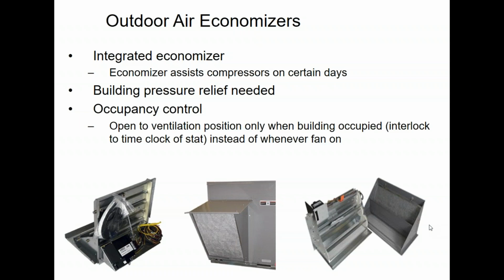Additionally, from a controls perspective, we need to have the ventilation damper close at night. Now, most of you guys know the economizer has two jobs. One is free cooling. The other one typically is to bring the outside ventilation air that's required for IMC or Chicago code or Wisconsin code or ASHRAE 62.1, whatever you're following. There's a certain amount of outside air you have to bring in. We'll talk about that in a few minutes.